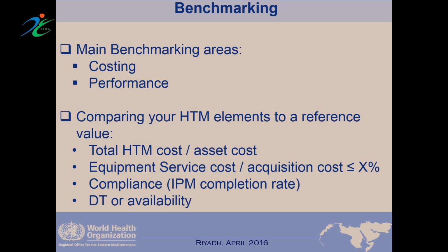Then also the downtime and the availability, to see how much time the equipment is down at my hospital, and what percentage I have available, working and functioning. This could be the last example, just to show you: if we take the ICU ventilator, as we said, the inspection interval is 6 months and the expected life is 10 years.